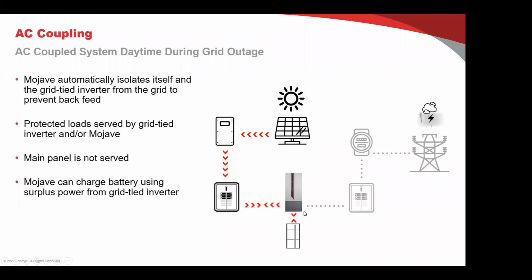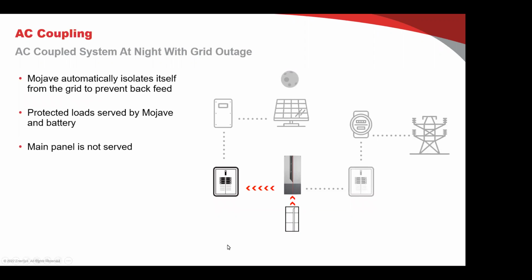So when we have a power outage, our inverter becomes a heartbeat, if you will, that the grid-dependent inverter can synchronize to. That allows it to keep producing PV during the solar day and power the backup load panel. If the panel needs more energy than what's available from the PV array, then we'll bring in some power from our battery and blend it in with the renewable energy. Then if the energy is more than what's needed during the day, we can use that to charge our batteries. It basically works very similar to being grid tied, except we've become the new grid, if you will. And then at the end of the solar day, it's used like an off-grid emergency backup power application, so we're powering the loads at night until the next solar day.